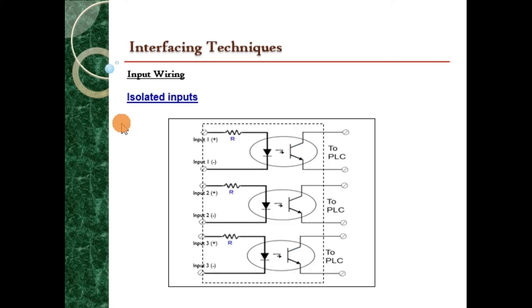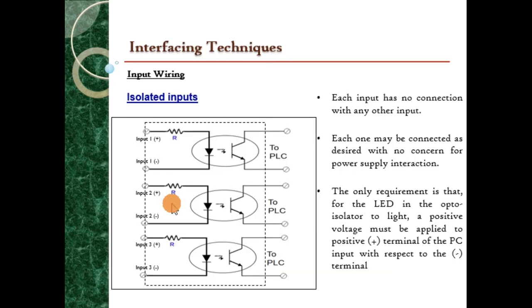Now we look into the isolated inputs. This is a diagram of the isolated inputs. Each input has no connection with any other input. Okay, they are isolated. So input 1 has no connection with input 2, and input 2 has no connection with input 3 or 1. Each one may be connected as desired with no concern for power supply interaction. The only requirement is that for the LED in the opto-isolator to light, a positive voltage must be applied to the positive input terminal with respect to the negative terminal.